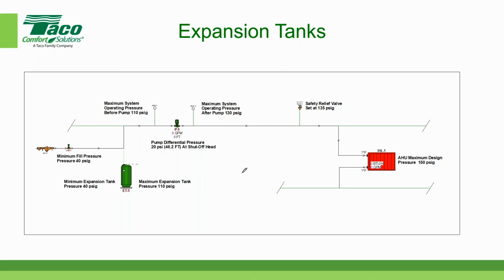A couple other great questions. What happens if you oversize the expansion tank? Oversizing an expansion tank has no negative effect on the operating characteristics of the system. The penalty for oversizing the tank would be physical size, how much space it takes up, and cost. If I put in a tank that's twice the size of what I need, in our example, we said we needed a tank that's roughly 100 gallons with an acceptance volume of roughly 53 gallons. If I put in a tank that's twice that size, then the maximum pressure obtained by the system will be less than 110 pounds, so that won't affect the system operating characteristics. However, the tank would be twice as big. It would consume more real estate and cost more money. So the only downside is that it's physically larger and costs more money. There's no negative effect to the system.